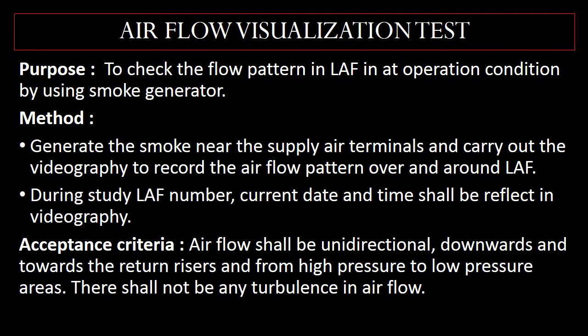The first important qualification test is the air flow visualization test. The purpose of this test is to check the flow pattern in the laminar air flow system under at-operation condition by using a smoke generator. In this method, smoke is generated near the supply air terminals and videography is carried out to record the airflow pattern over and around the laminar air flow system. During this study, the laminar air flow number, current date, and time shall be reflected in the videography.